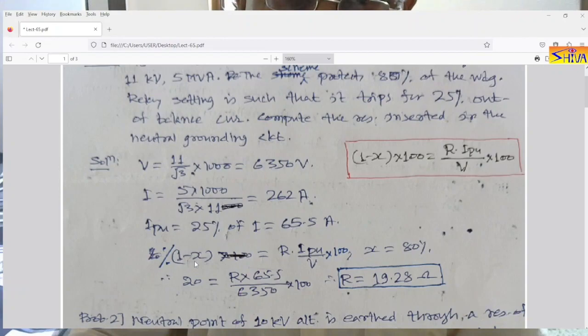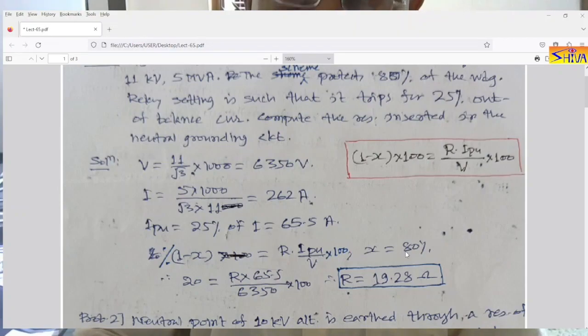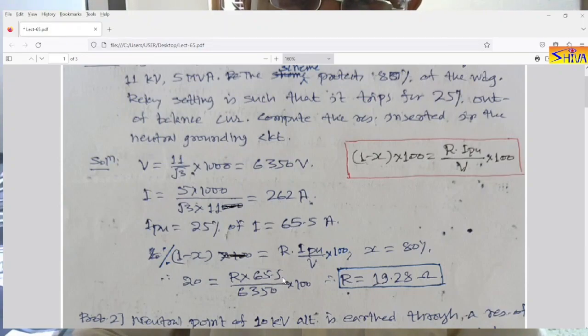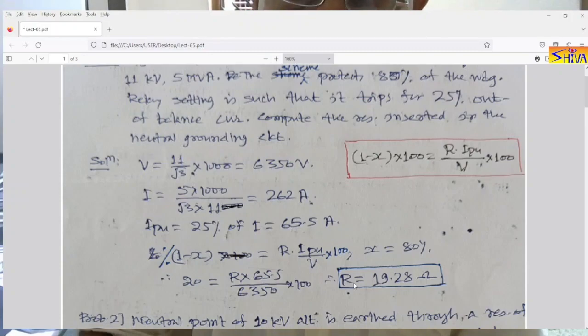Using the formula: percentage of winding unprotected = R × I_pickup / V × 100. The percentage of winding protected is 80%, so the unprotected portion is 20%. Therefore: 20 = R × 65.5 / 6350 × 100. Solving, the resistance inserted in the neutral grounding circuit is 19.28 ohms. That is the answer.